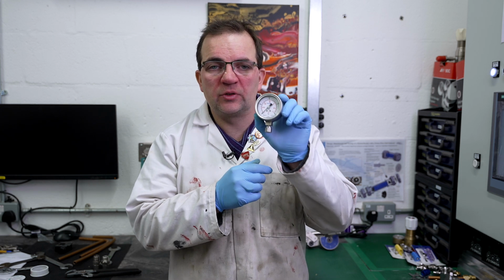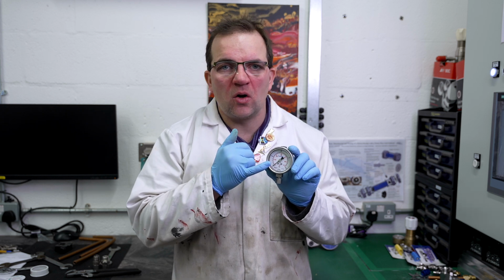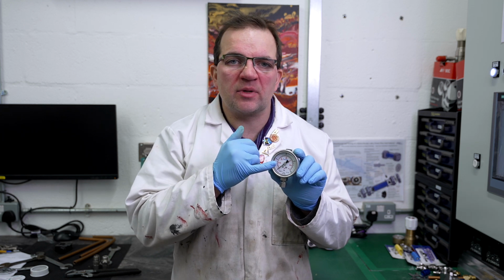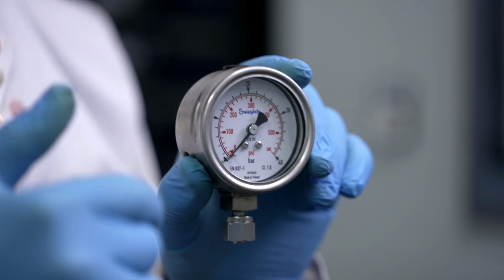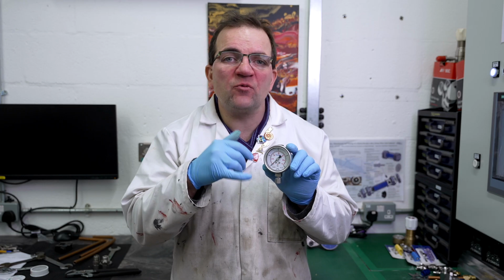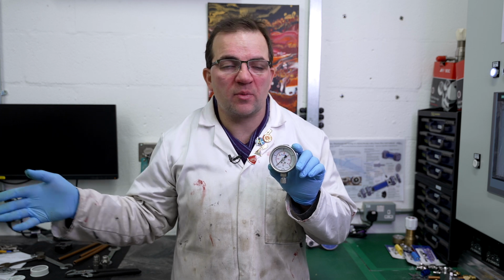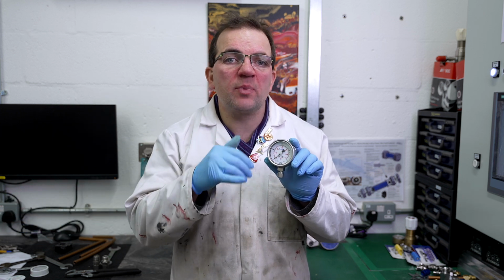One important thing to note when dealing with gauges is that they are measuring the pressure above atmosphere. So when you see 1 bar on a gauge like this, you are measuring 1 bar above the atmosphere. We call this 1 bar gauge, 1 bar with a capital G for gauge. In reality, if you were to compare this with a vacuum environment, where the pressure is almost 0, it would be 2 bar absolute. So we call that bar absolute, or bar capital A. So there is always a difference between bar gauge and bar absolute.